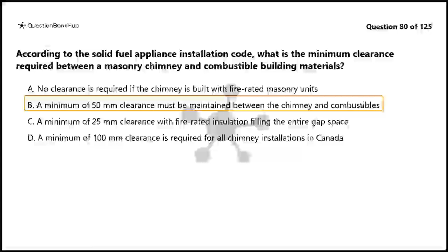The correct answer is B. A minimum of 50 mm clearance must be maintained between the chimney and combustibles. The Solid Fuel Appliance Installation Code requires a minimum of 50 mm, 2 inches, clearance between a masonry chimney and any combustible building materials such as wood framing, insulation, and sheathing. This air gap prevents heat transfer from the chimney to combustible materials.